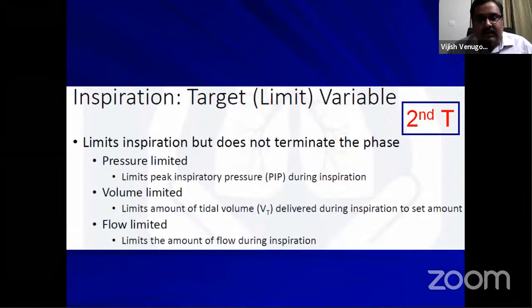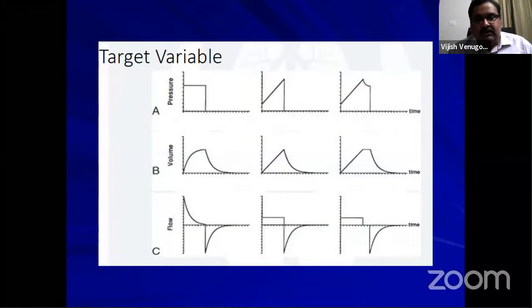The second T is the target, or something called the limit variable. The correct terminology is limit variable. We can remember it as the second T, that is targeting. What it does is it limits inspiration, but it does not terminate the phase. It could be pressure limited, volume limited, or flow limited. That is, it will limit the peak inspiratory pressure during inspiration. If it is volume limited, it will limit the amount of tidal volume delivered during inspiration. If it is flow limited, it will limit the amount of flow during inspiration. So these are the three different forms of limits that are available.